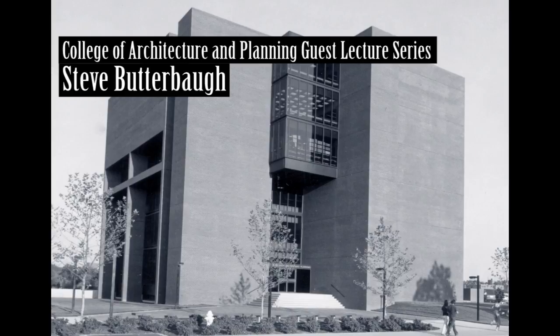The mechanical man is interested in the type of system used for heating and cooling. He measures the velocity of the air coming from the air handlers. He checks steam and air temperatures, the RPMs of fans, and the amperage of motors. He finds out the hours of the day the building is in use.